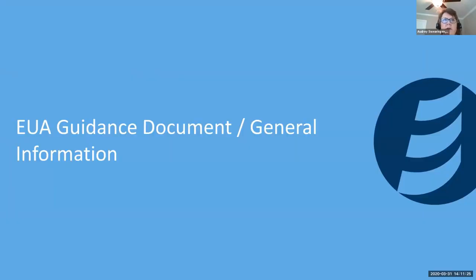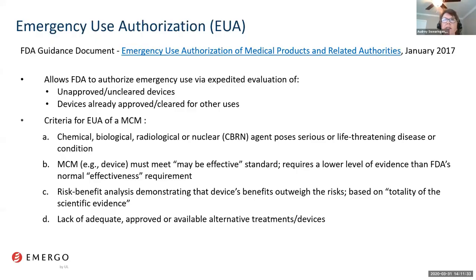So I want to go through some of the guidance document elements for an emergency use authorization. Next. I provided a link to the guidance document that was issued in 2017. It again allows the FDA to authorize emergency use via expedited evaluation of devices that have not been previously approved or cleared, as well as those that are approved or cleared, but for other uses. There's four criteria for an emergency use authorization of a medical countermeasure product. They are listed here. I'm not going to go through all of them. Suffice it to say that COVID-19 meets all of these criteria. The one I do want to point out right now is that the MCM must meet a standard of it may be effective, which is a lower level of evidence than the normal effectiveness requirement under a normal situation. Next, please.